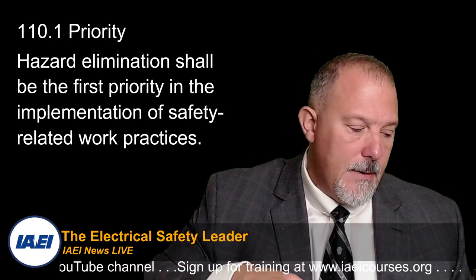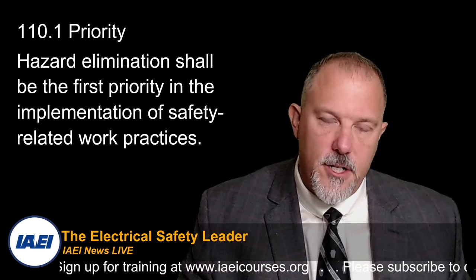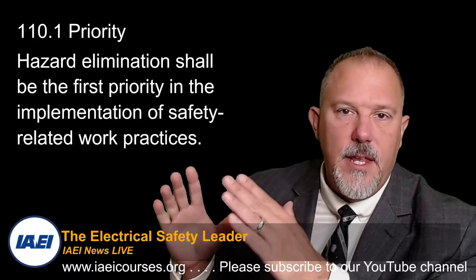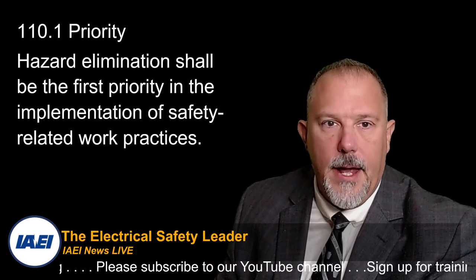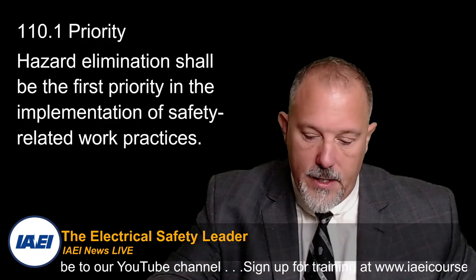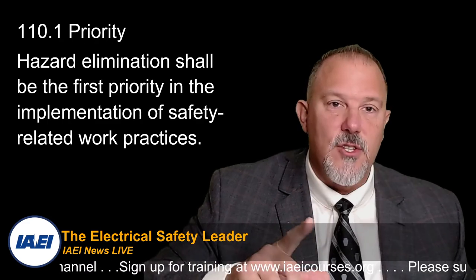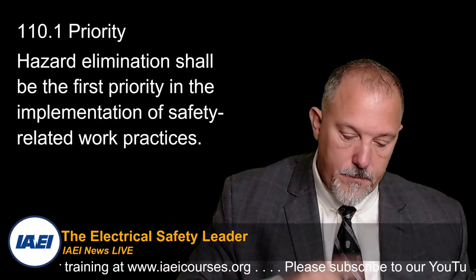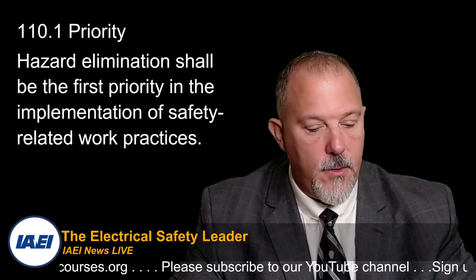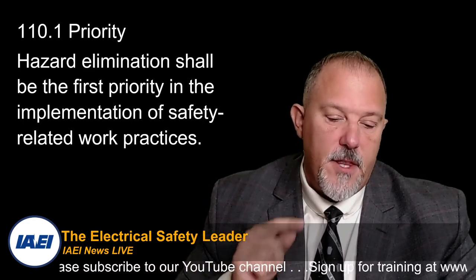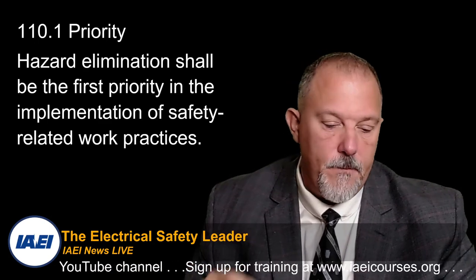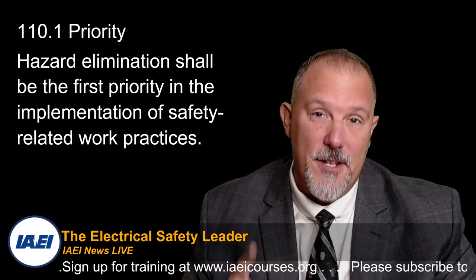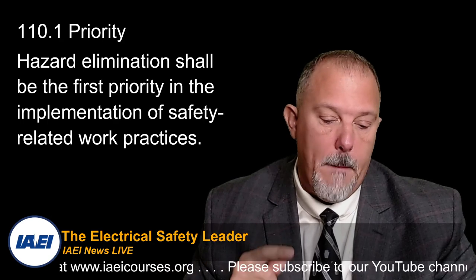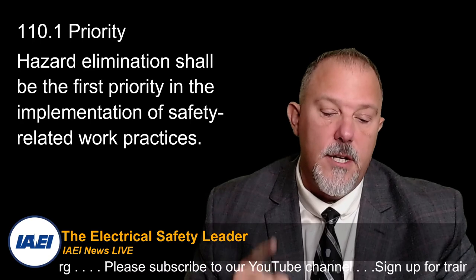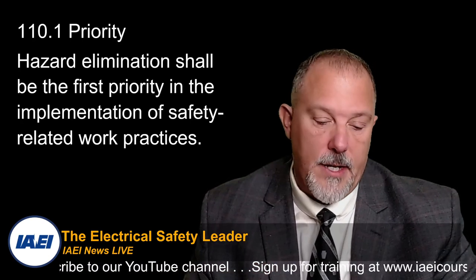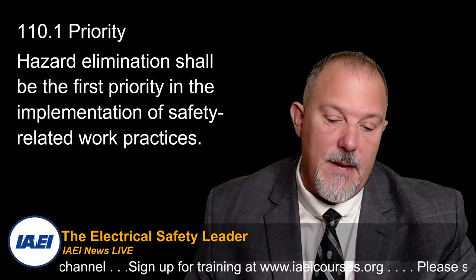But they reorganized 70E in this 2021 version or edition of this standard, and they raised the awareness that your number one priority has to be elimination of the hazard. Now, if you look at 110.1, because 110.1 doesn't stand just on its own, they have two informational notes. And I want to read those because I think they're very critical for our discussion here. Hazard elimination shall be the first priority in the implementation of safety related work practices. Informational note number one says, elimination is the risk control method listed first in the hierarchy of risk control identified in 110.5(H)(3). And they're pointing us back to Annex F for examples of hazard elimination.